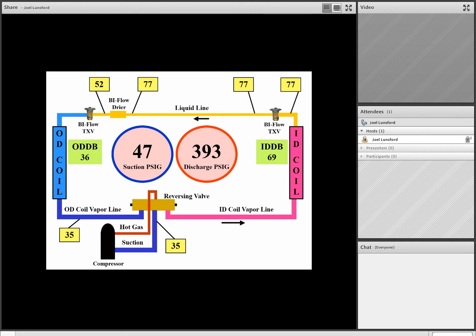But hang on a second, look at that. We've got a 25-degree temperature drop across our BiFlow filter dryer. Large temperature drop across our filter dryer. And so we know we have a restricted filter dryer in this example.